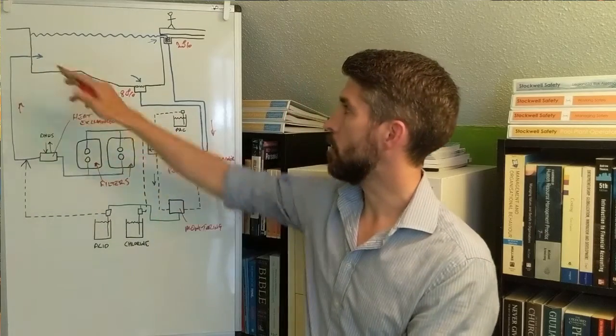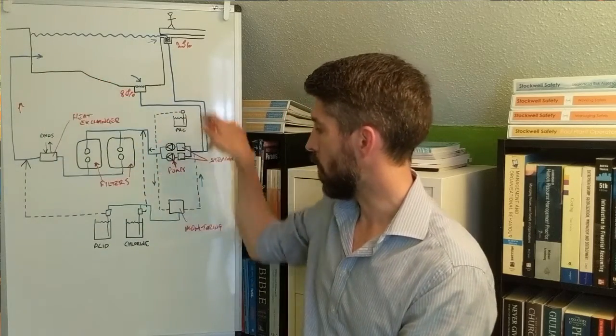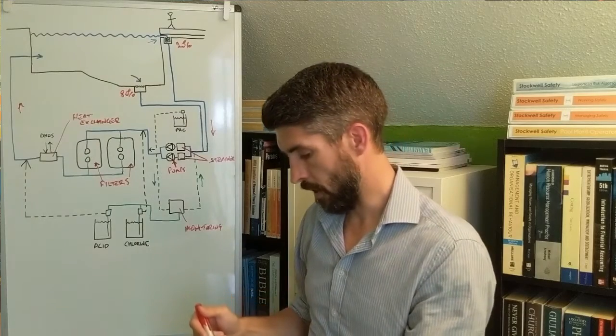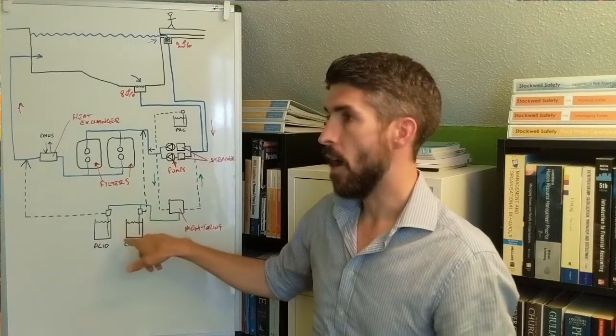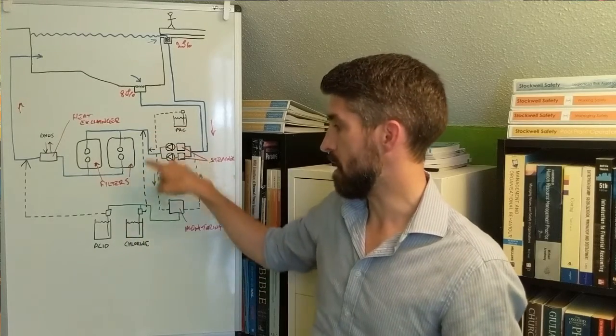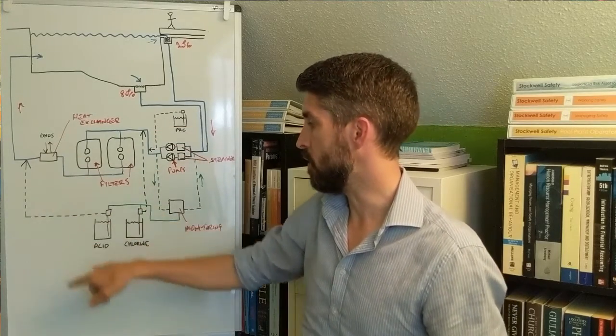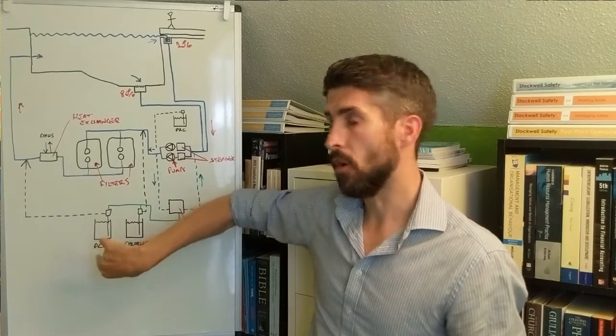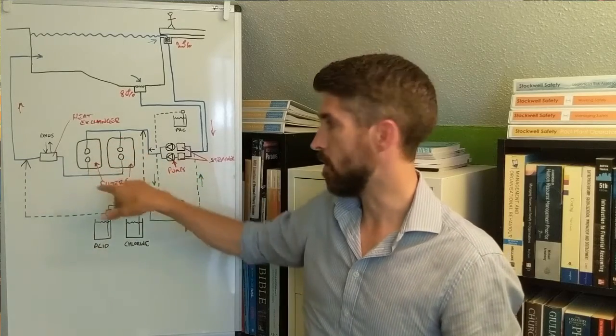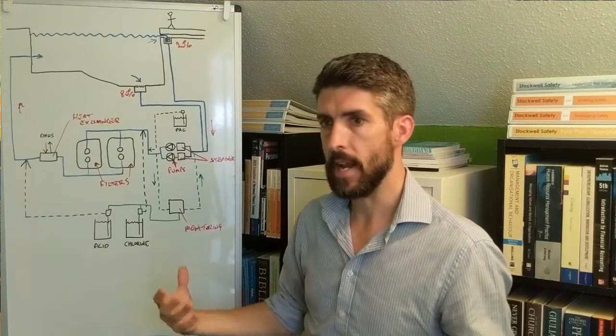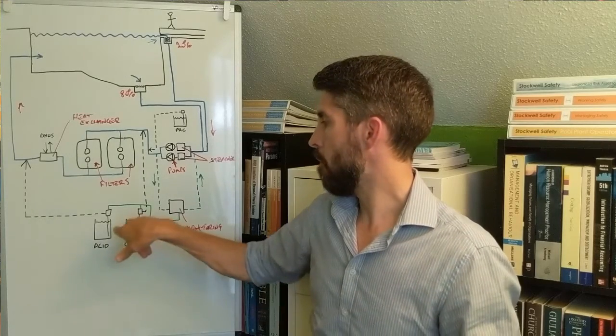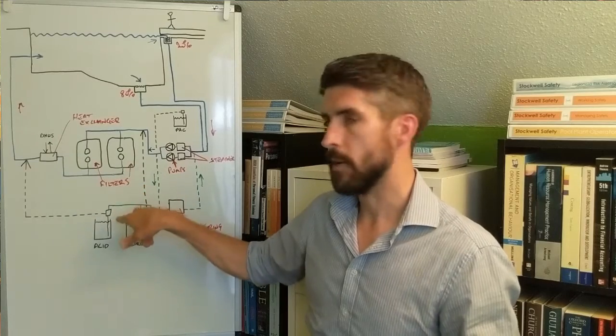The acid is usually the final thing to be dosed into the system prior to it going back to the pool. So it's a complete circuit. It's very important, I think, for pool plant operators to be aware of where the chlorine is being dosed and where the acid is being dosed, because if you get those two mixed up, even in the pipework, there's been incidents of chlorine and acid being combined in the pipework and creating a chlorine gas incident.